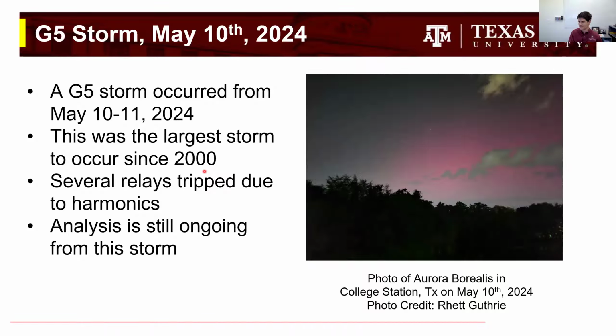Several relays did trip due to harmonics, mostly capacitor and capacitor bank relays, I think. I don't have the details. Bob at EPRI and his team are working with utilities, still trying to figure out whether it was just nuisance tripping or whether there was an actual underlying GMD cause. They're still doing root cause analysis, but there were definitely more trips observed during this storm than normally would be expected.